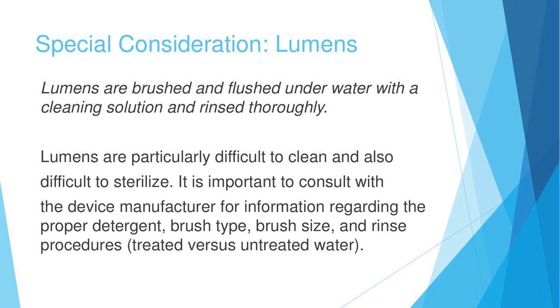One of the areas that we need to pay attention to is our lumens. Lumens are brushed and flushed underwater with cleaning solution and rinsed thoroughly. Lumens are particularly difficult to clean and also difficult to sterilize. It's important to consult the device manufacturer for important information regarding the proper detergent, brush type, brush size, and rinse procedures, meaning either treated or untreated water.